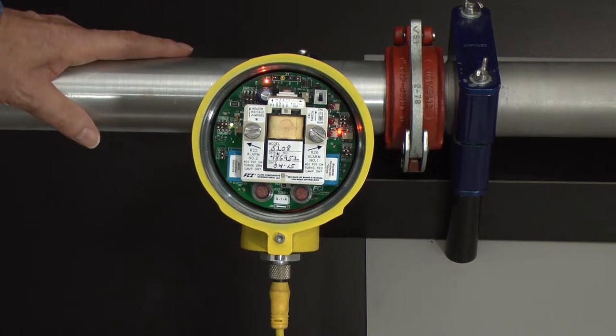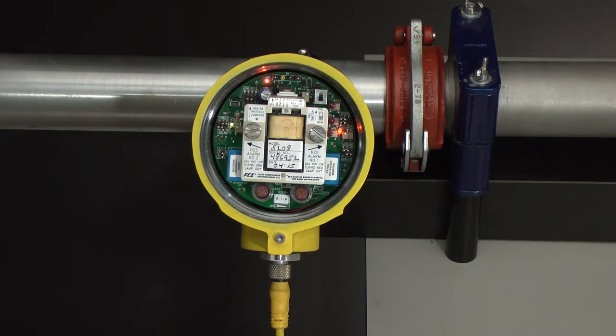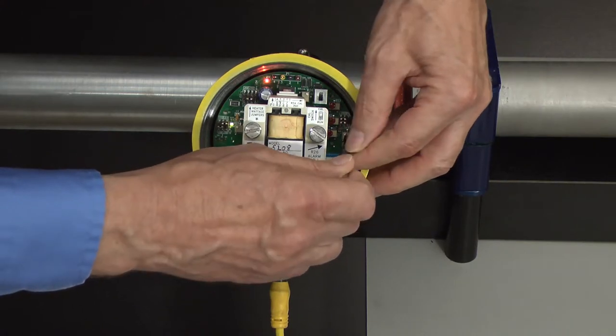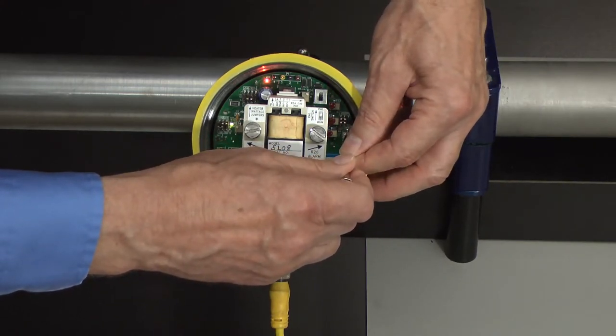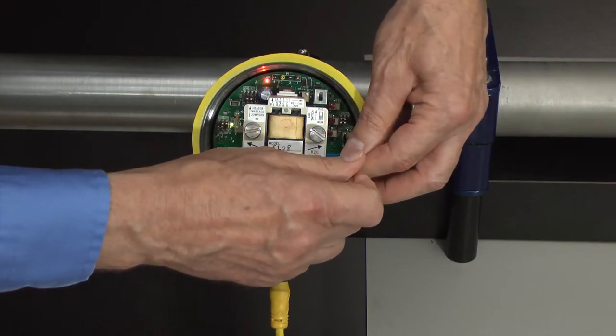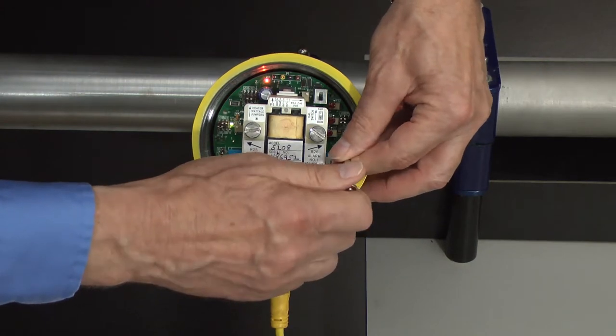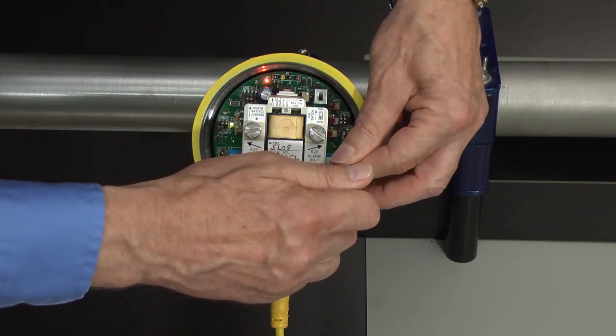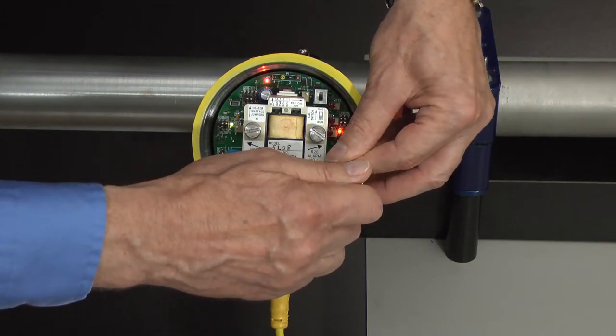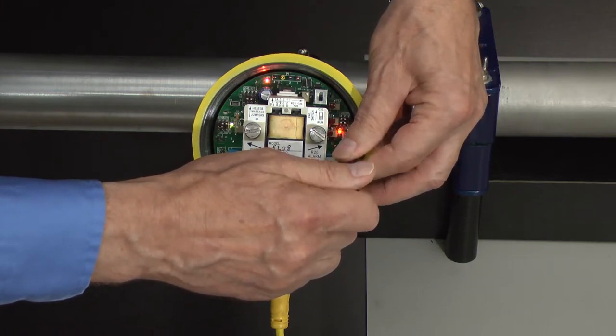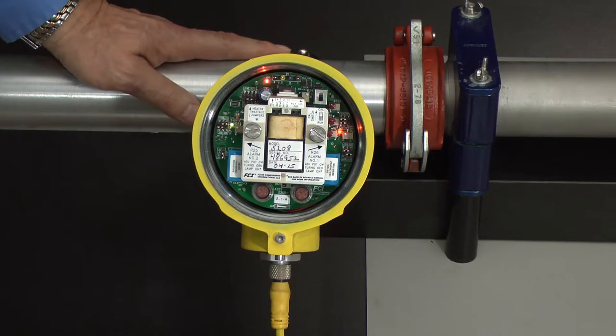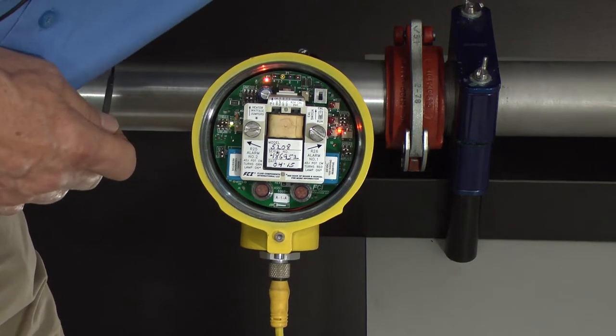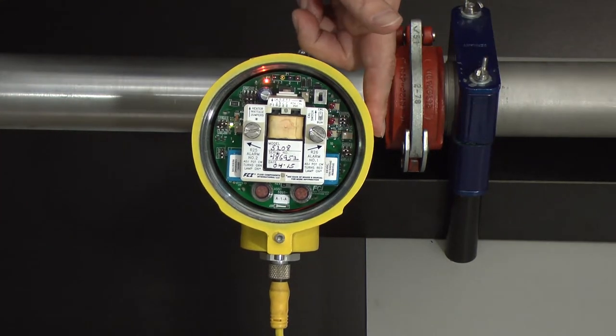You have a line here that has no flow in it, and so the LED is on indicating no flow, and what I want to do for the relay alarm is I just want to turn the set pot here to make the light go off. I just want to make it be able to go off and on so I know I'm right on the set point like that. And then I'm just going to leave it in the on position because on always indicates a loss of flow and there's no flow in the pipe. So I want to leave it in that condition. Now I get a very fast response time. If the safety relief valve blows, I have my alarm just that fast.